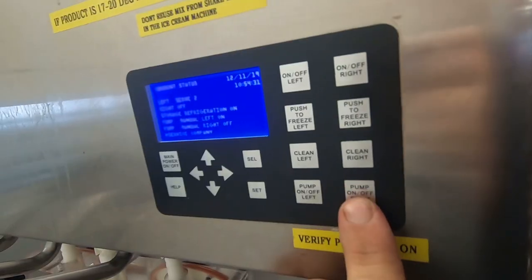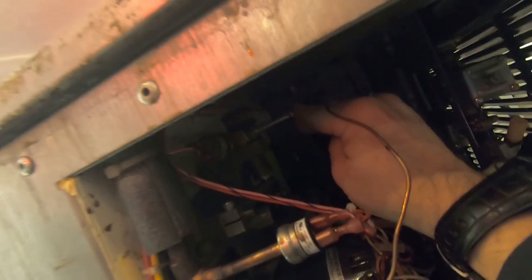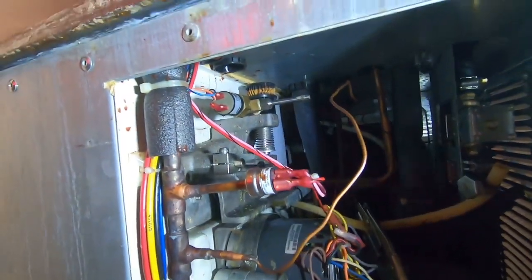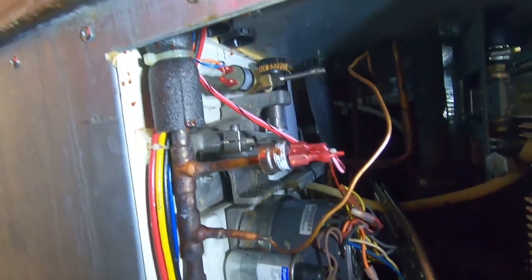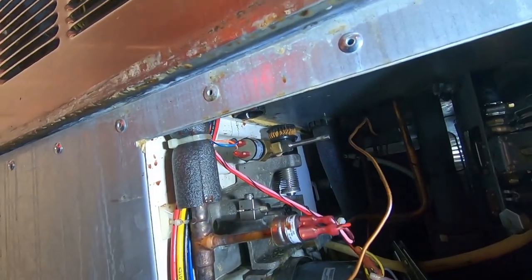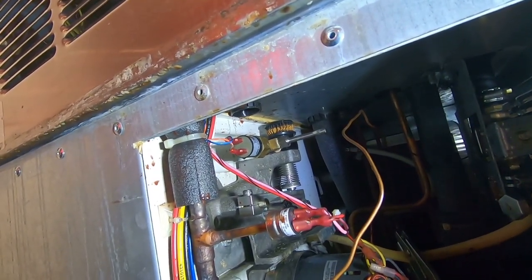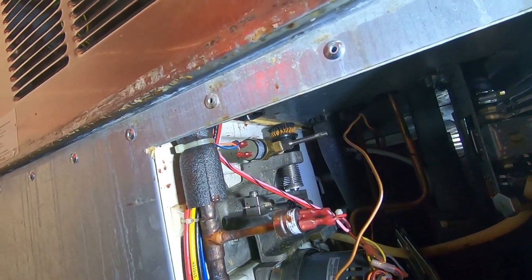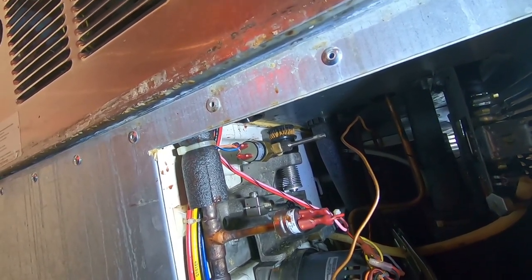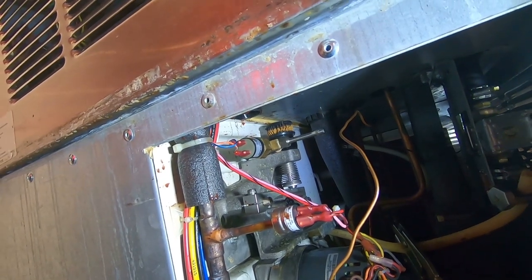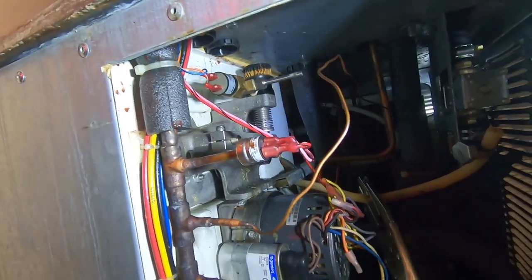Basically hit your pump on, clamp that off, put your finger over it, and it's not shutting off. It should shut off in three seconds and there's no air at all coming out. This is probably the worst thing about this machine, this pump's tendency to let the mix back past the check valve and into the piston area. I've rebuilt this pump probably at least four, five, six times and if there's one thing I would change, it would be that right there. They did change it on the new machines.